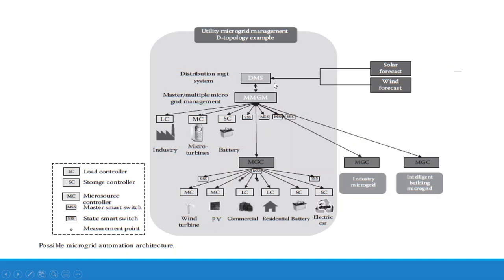Then there is the master or multiple microgrid management system, MMGM, which will be working in coordination with the distribution management system. And then this microgrid management system is going to control your load controller, micro source controller, then storage controller, then static smart switch. It will be controlled by the master grid management system. It could be your master smart switch. There could be several master smart switches and static smart switches it would consist of.